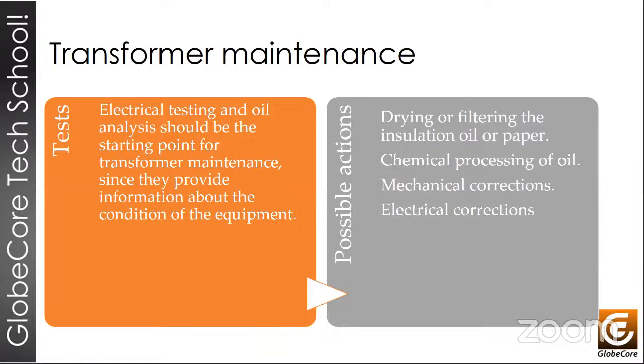I want to be very clear on this. Prior information is always required to perform maintenance. It sounds very strange when someone says that they have to do routine oil filtration every year, or that the oil is regenerated on a date in a calendar. We're going to regenerate the oil on a certain date, like on this day, we're going to treat the transformer because this date has come. That's a bad approach. We must carry out maintenance of the transformer based on the information we collect.